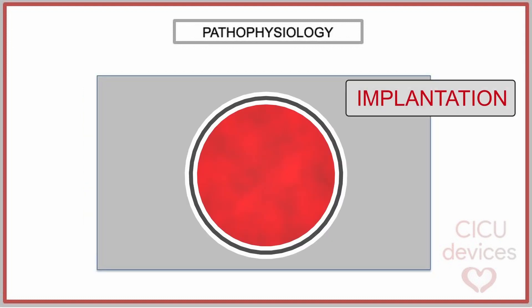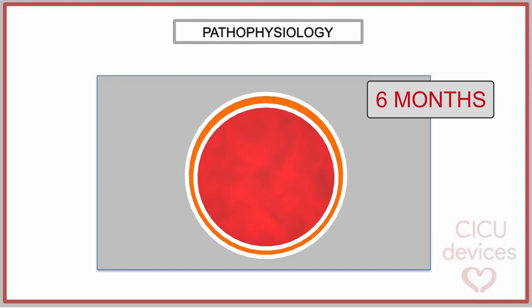This is an animation to illustrate how this process unfolds over time. At the time of implantation, the space between the outflow graft and bend relief is not occupied. However, over time, this space becomes filled with acellular biodebris.